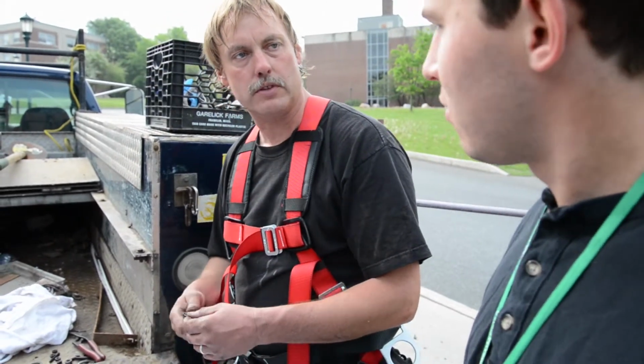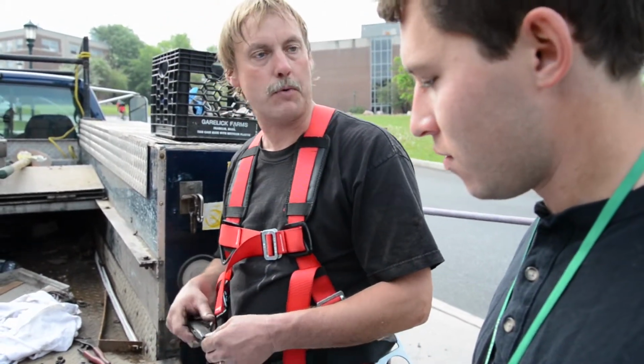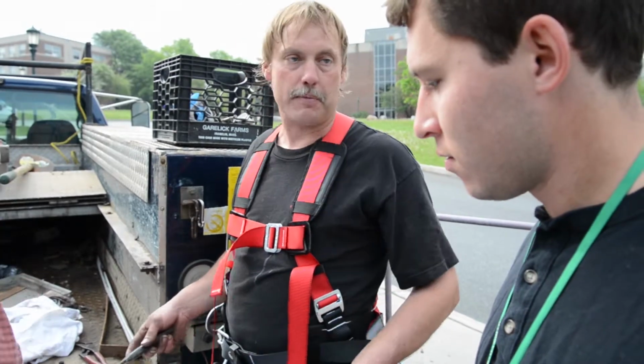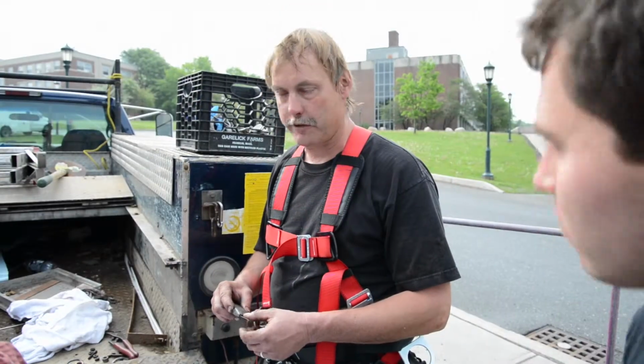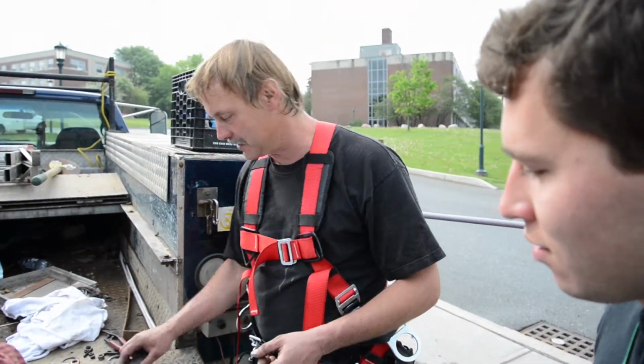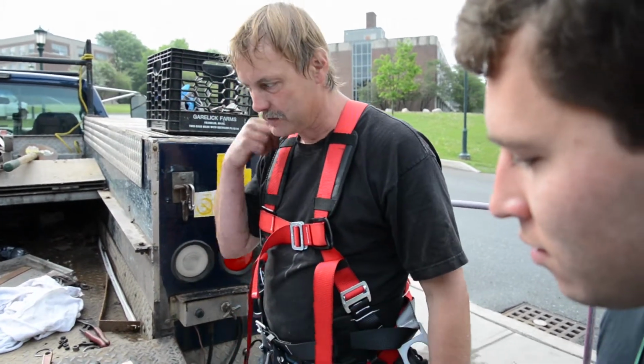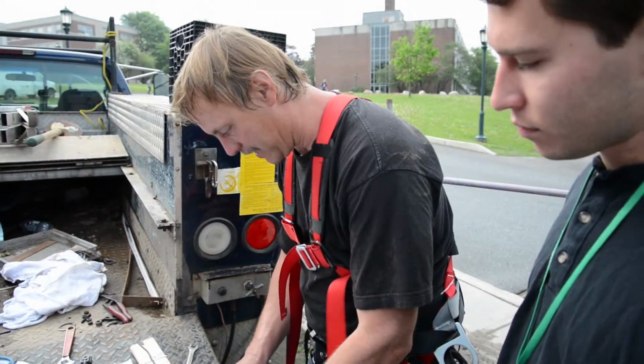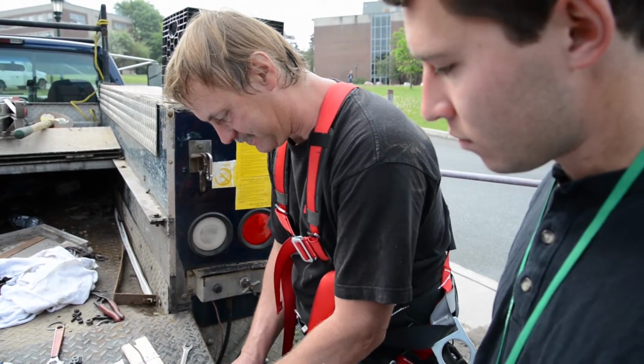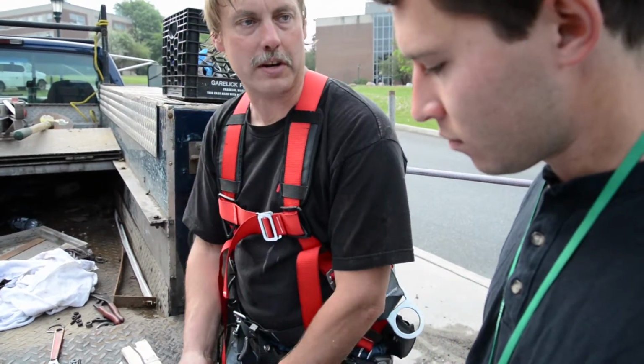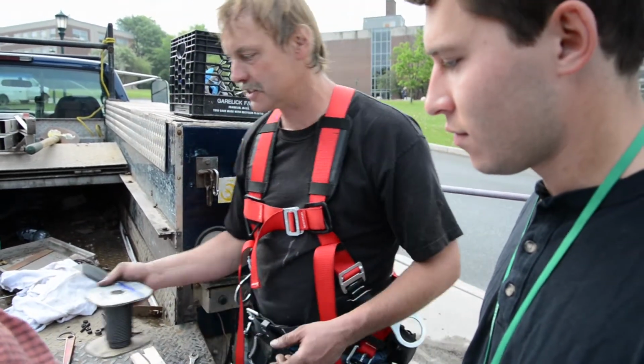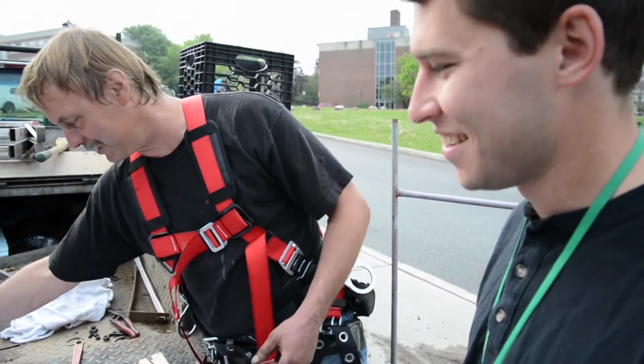But with high pressure steam, we can't really afford to let them go that long. You know, some people will buy these and put them in and leave them in for 15 years. Yeah. You can't afford to do that with high pressure steam. Yeah. It's asking for problems. Right. But to enter a manhole and tighten a bonnet is, you know, more work than you want to do when the steam is on and it's 135 degrees in the vault.